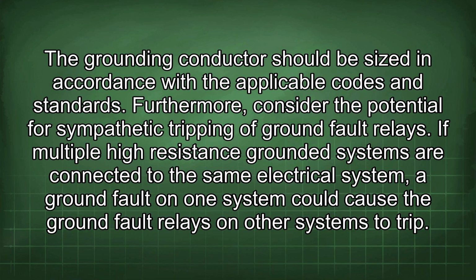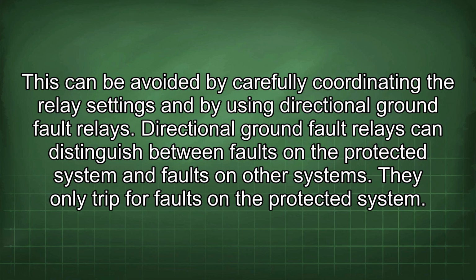Furthermore, consider the potential for sympathetic tripping of ground fault relays. If multiple high-resistance grounded systems are connected to the same electrical system, a ground fault on one system could cause the ground fault relays on other systems to trip. This can be avoided by carefully coordinating the relay settings and by using directional ground fault relays. Directional ground fault relays can distinguish between faults on the protected system and faults on other systems. They only trip for faults on the protected system.